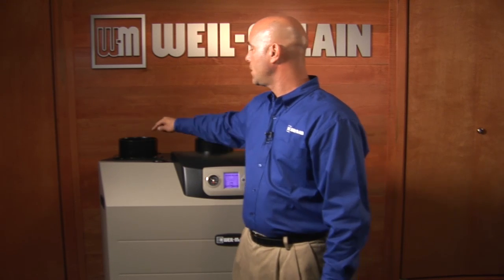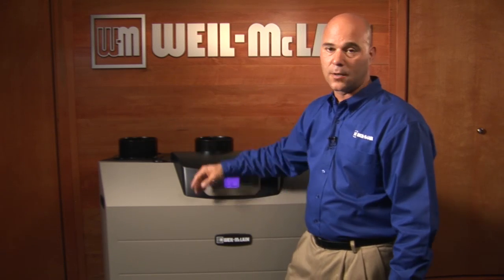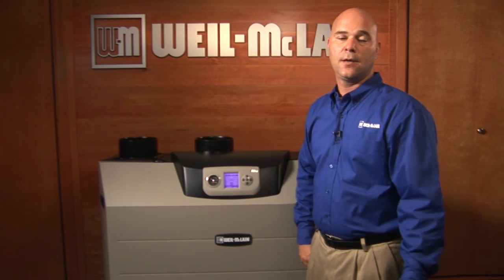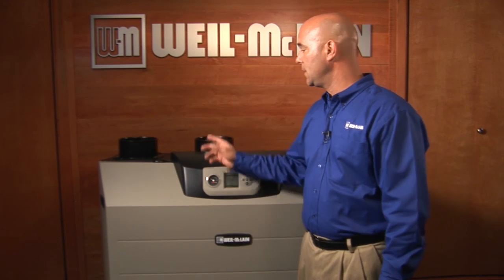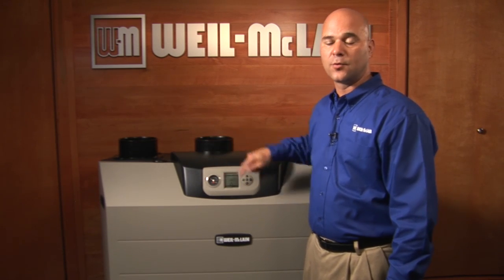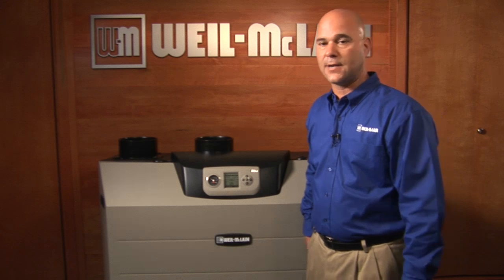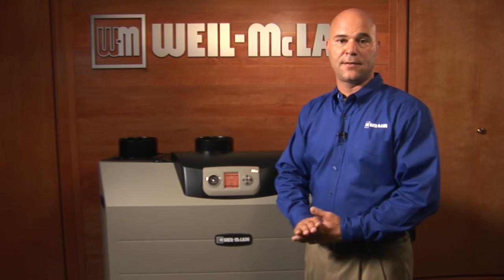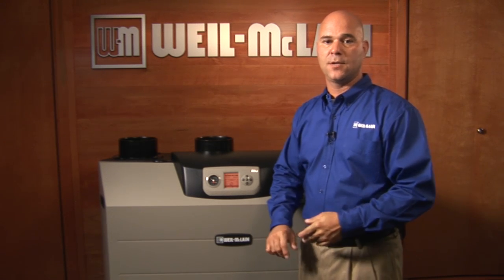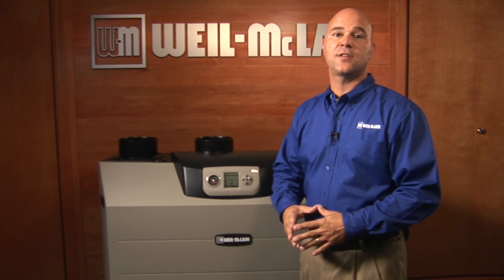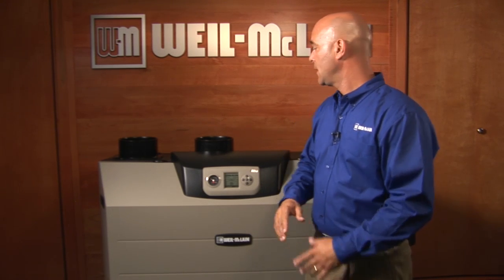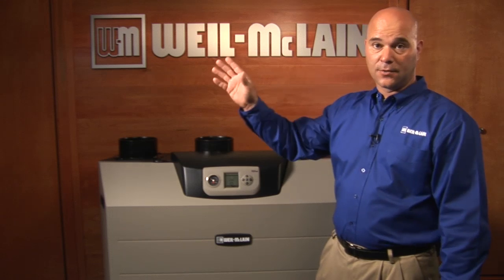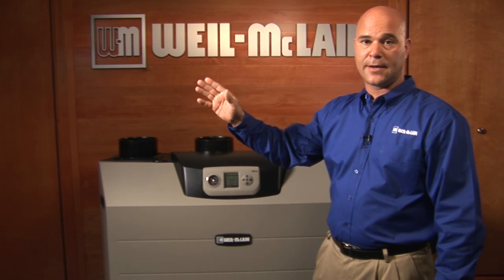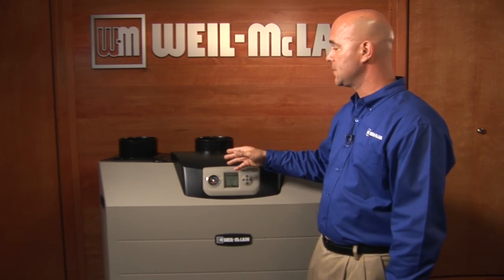The exhaust port has an integral drain, so any condensation into PVC piping or any rainwater that runs back from the exterior of the building down into the exhaust port will be caught in the trough and brought over and connected into the condensate trap. It's PVC venting up to 100 feet with 2 elbows. It cannot be cellular foam core PVC. It can be sealed combustion with both pipes going to the exterior of the building or direct exhaust.